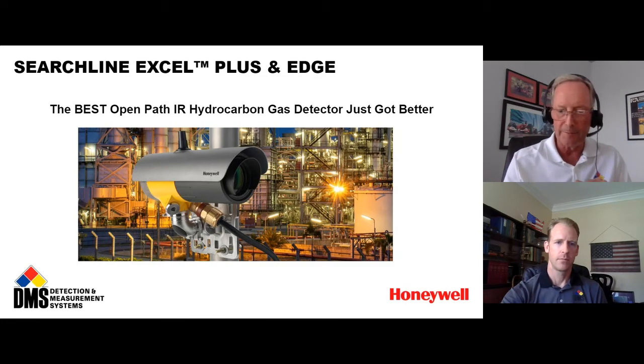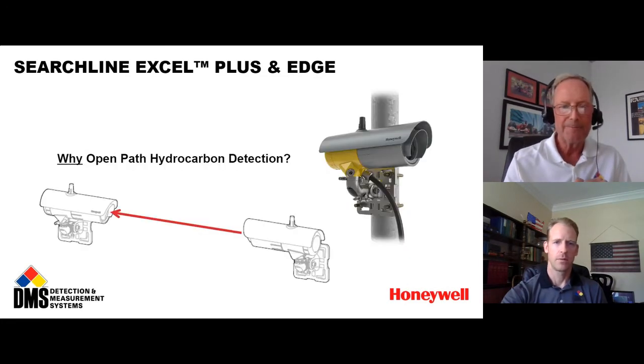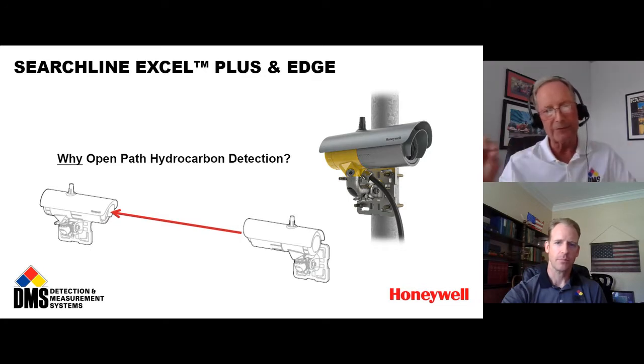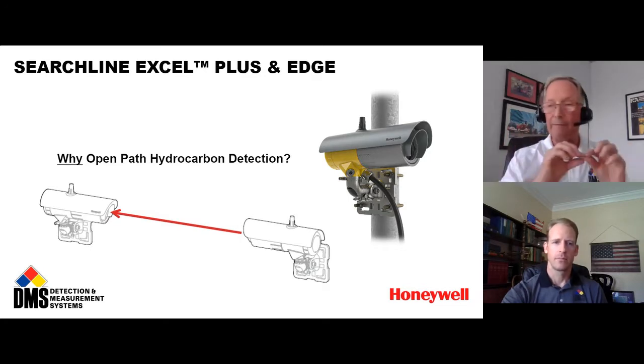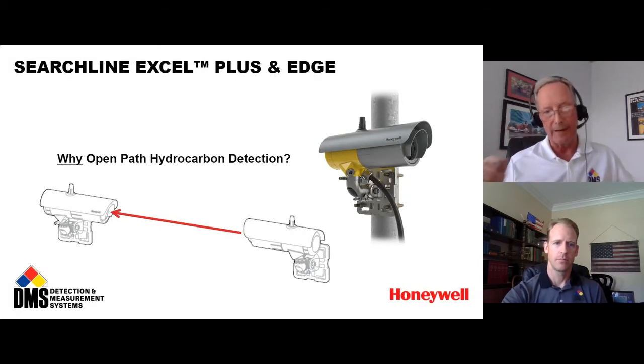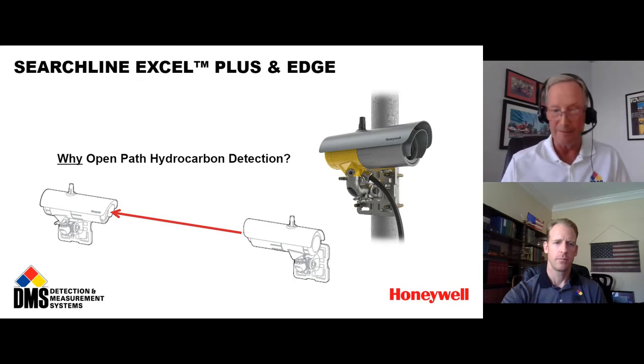And so with, pardon me, this moved. So with an open path infrared hydrocarbon detector, you have a continuous line of detection traveling hundreds of feet from the IR source to the IR receiver, which creates a much greater probability that the gas will actually encounter the detection beam or the detector, so that the likelihood of your gas detection system actually seeing the gas and having an opportunity to respond and alarm to the gas is just astronomically improved over point detection.